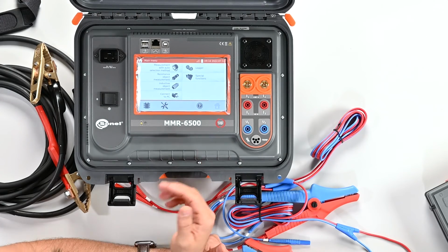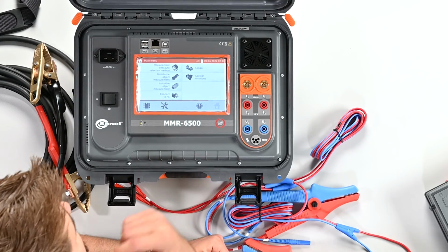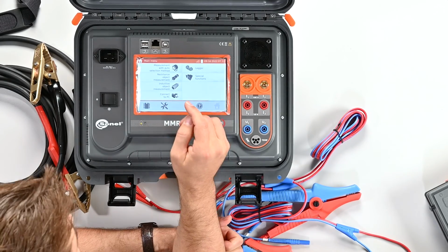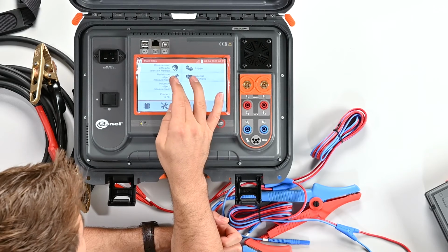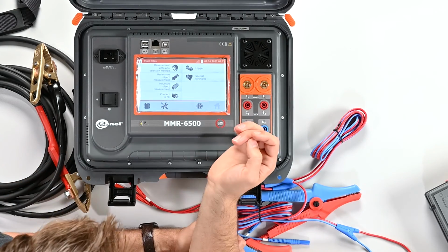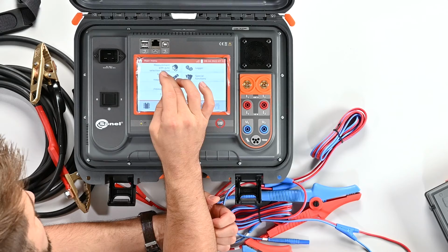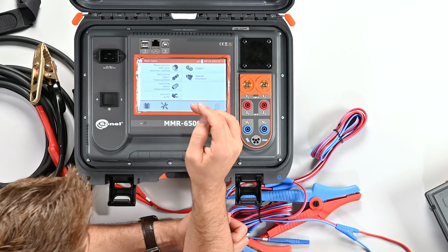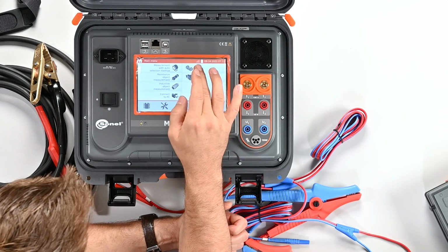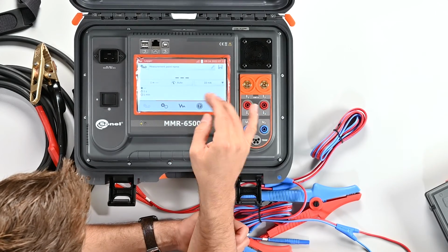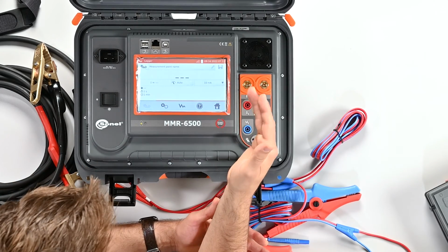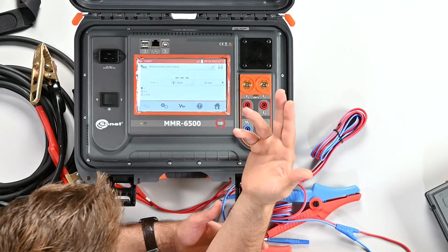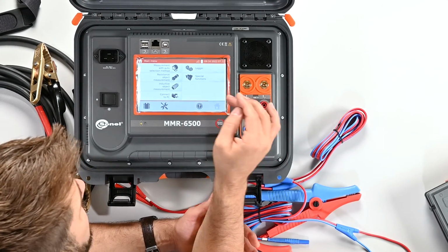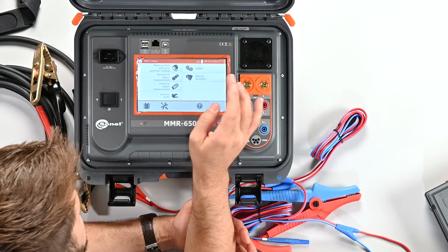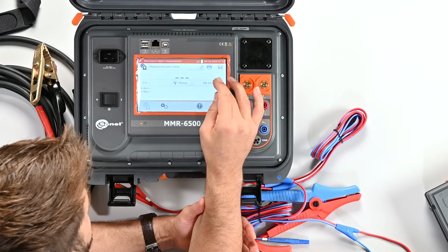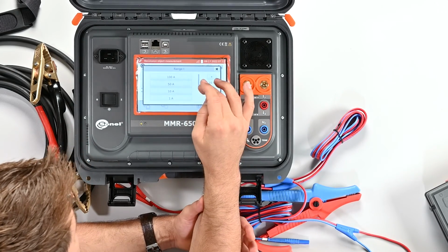Okay, we're going to look now at some of the features of these MMR instruments. On the main menu here, we have the option of, are we going to do a resistive object measurement or an inductive object measurement? Or if we don't know, we can do the auto selection measurement. And then also here we have the current logger. If we select the logger, it's going to plot us out a graph of how the resistance has changed throughout the time that we're testing. Now, let's say we're going to do a resistive object, push the button, drop down this menu, select the test current.